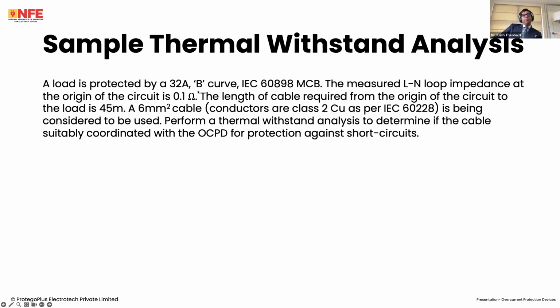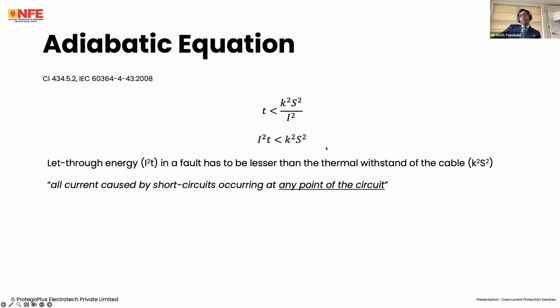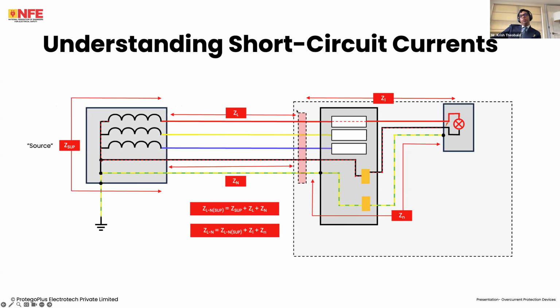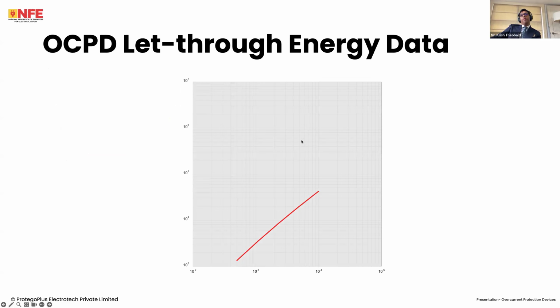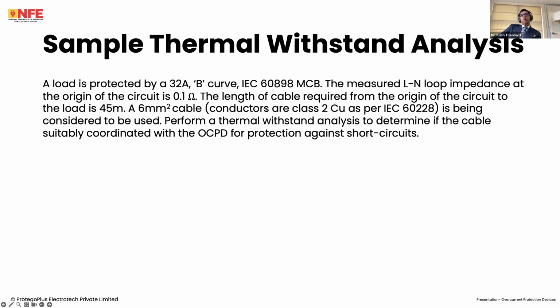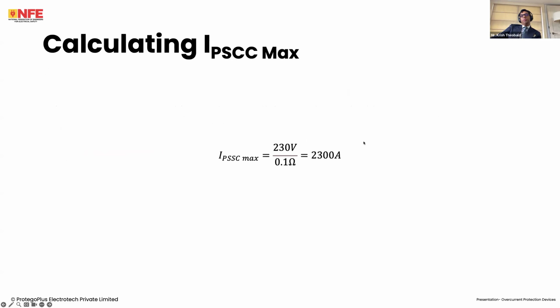Look at a sample example. A load is protected by a 32 amp B curve 60898 MCB. The measured line to neutral impedance at the origin of the circuit here is 0.1 ohms. Length of the cable required from the origin of the circuit to the load is 45 meters. A 6 square mm conductor is being used, class 2. Perform a thermal withstand analysis to determine if the cable is suitably coordinated.